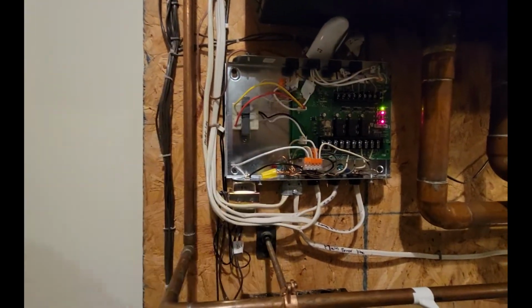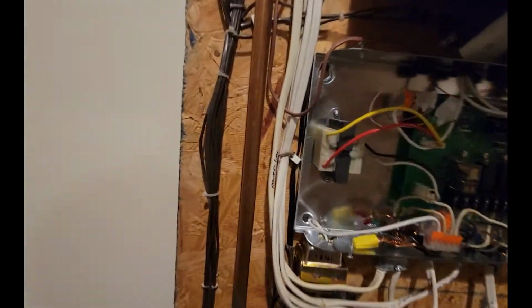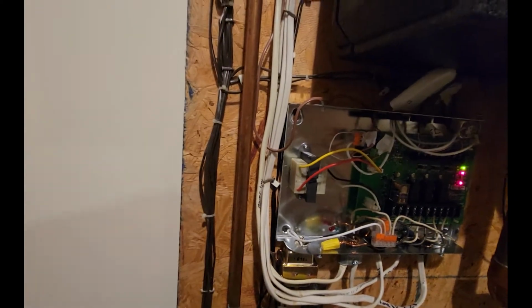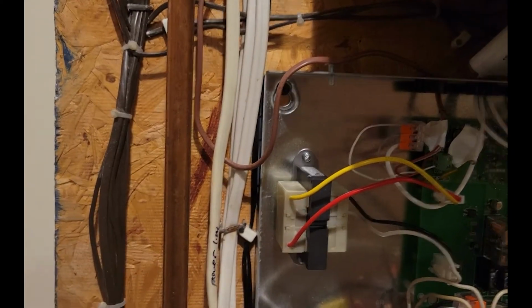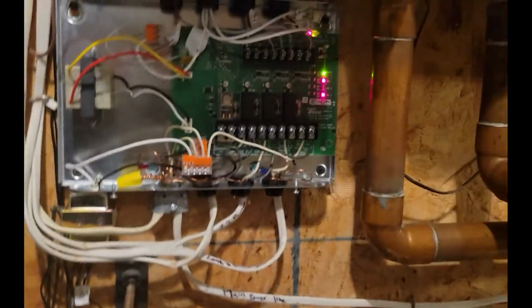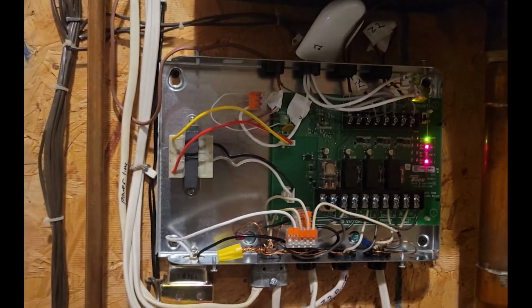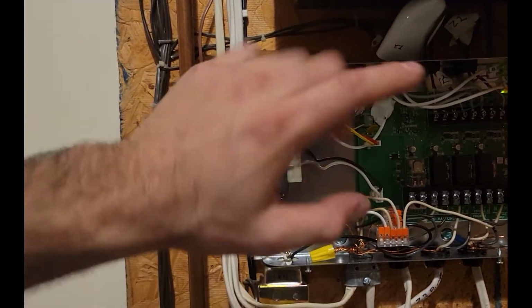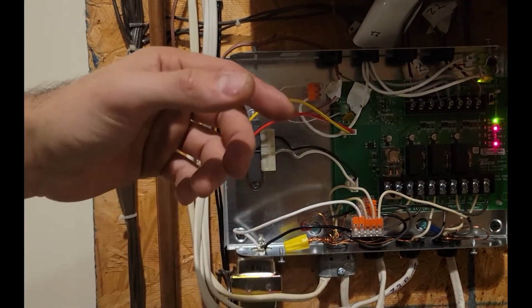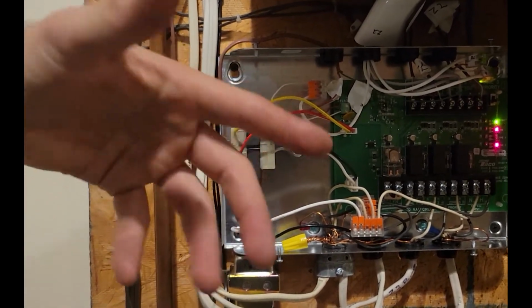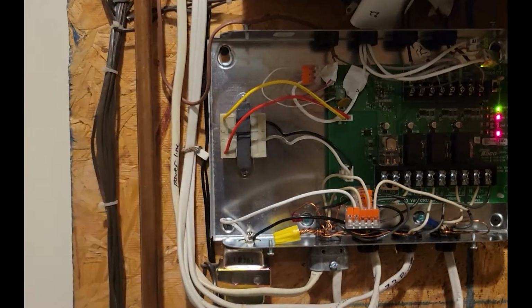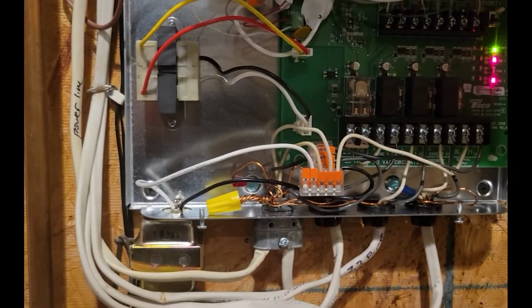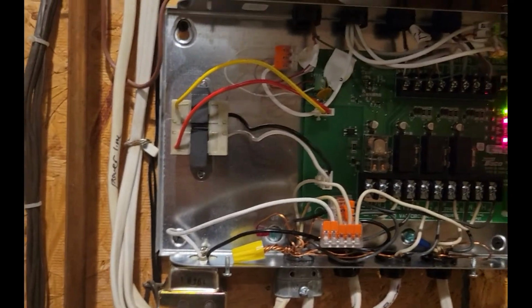So you can't necessarily do that, because these transformers are only rated for up to 15 VA. I don't know if you can tell, but right there you'll see the rating. They're only rated for up to 15 VA. So you can't put a bunch of different stuff on the transformer, because eventually, over time, it'll put way too much stress on it, and it'll just thermally break. The windings will overheat, break, and the transformer will be no good.